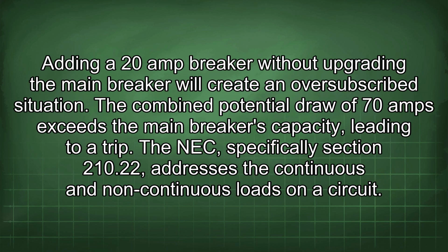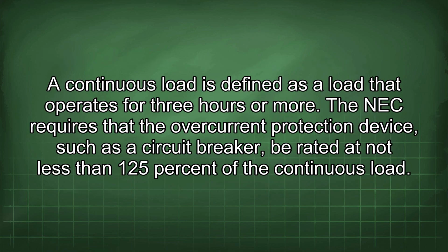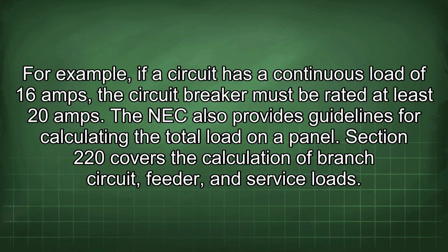Adding a 20 amp breaker without upgrading the main breaker will create an oversubscribed situation. The combined potential draw of 70 amps exceeds the main breaker's capacity, leading to a trip. The NEC, specifically section 210.22, addresses the continuous and non-continuous loads on the circuit. A continuous load is defined as a load that operates for 3 hours or more. The NEC requires that the overcurrent protection device, such as a circuit breaker, be rated at not less than 125% of a continuous load. For example, if a circuit has a continuous load of 16 amps, the circuit breaker must be rated at least 20 amps.